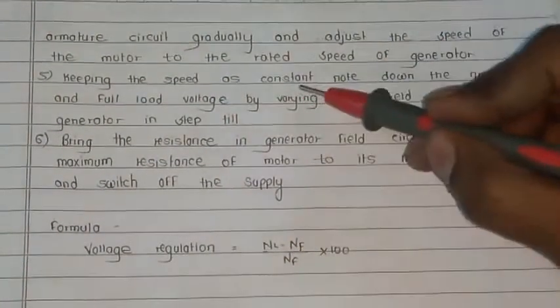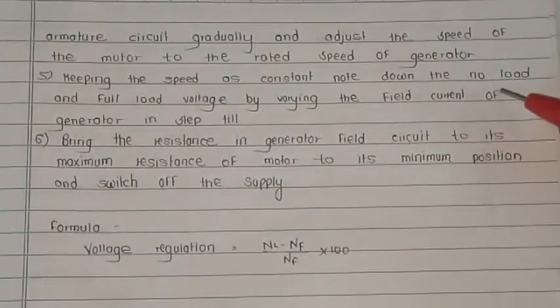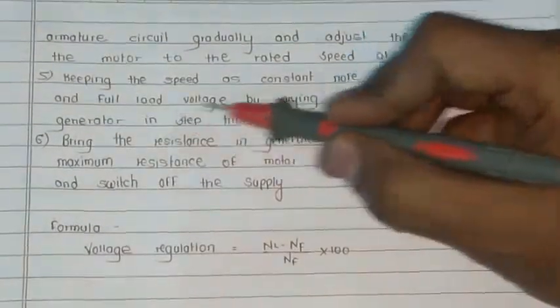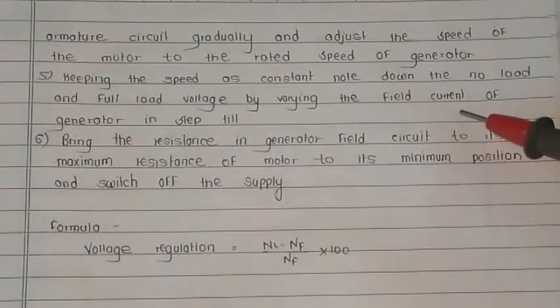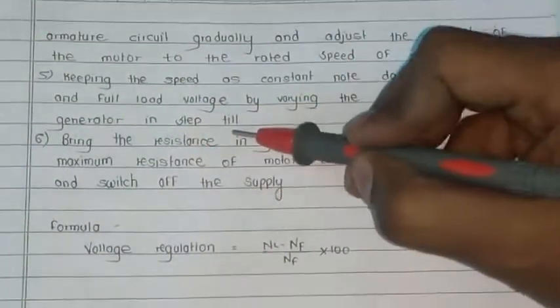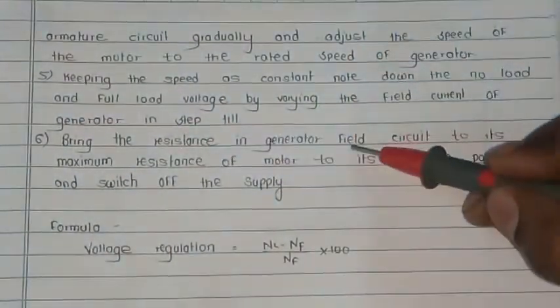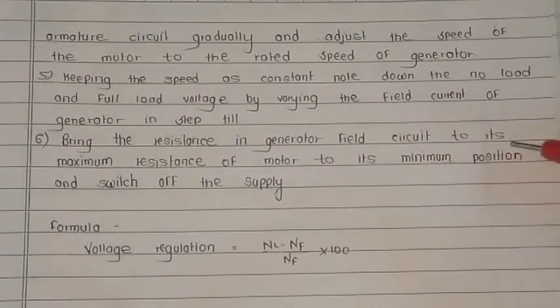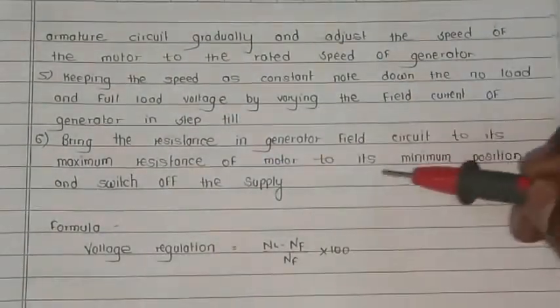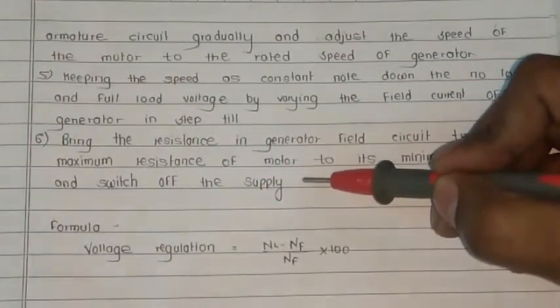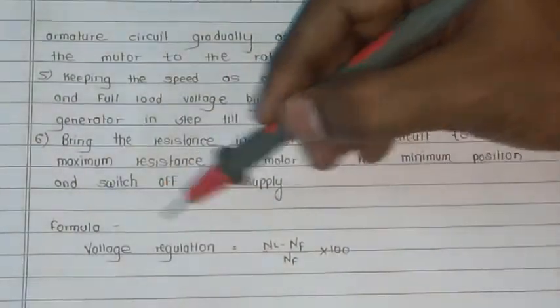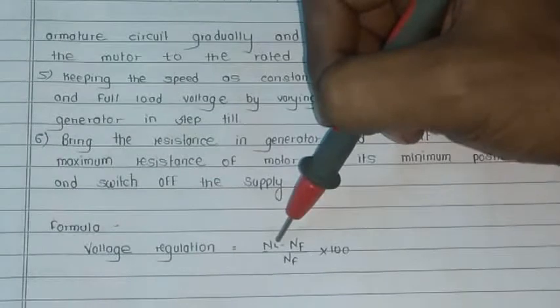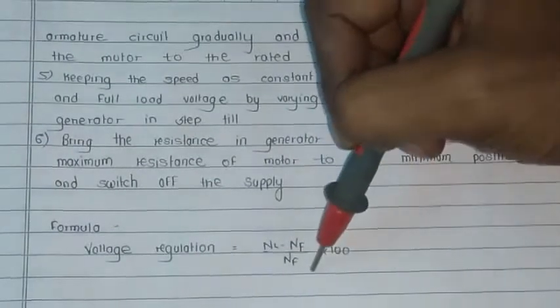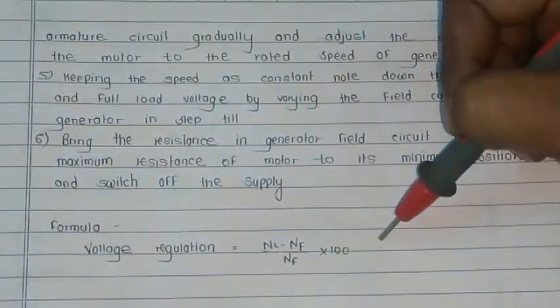Keep the speed constant. Note down the no load and full load voltage by varying the field current of the generator in steps. Bring the resistance in the generator field circuit to its maximum and the motor rheostat to its minimum position, and switch off the supply. And this is the formula for calculating the voltage regulation. Voltage regulation is equal to voltage at no load minus voltage at full load, divided by voltage at full load, multiplied by 100.